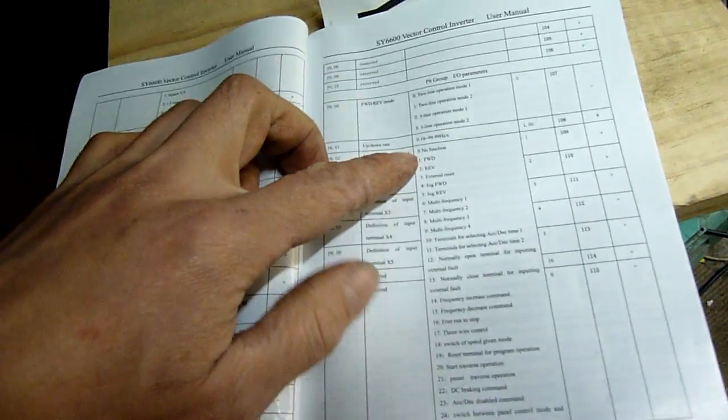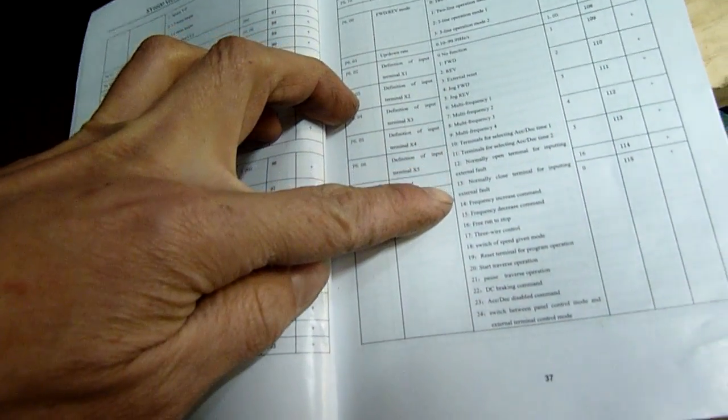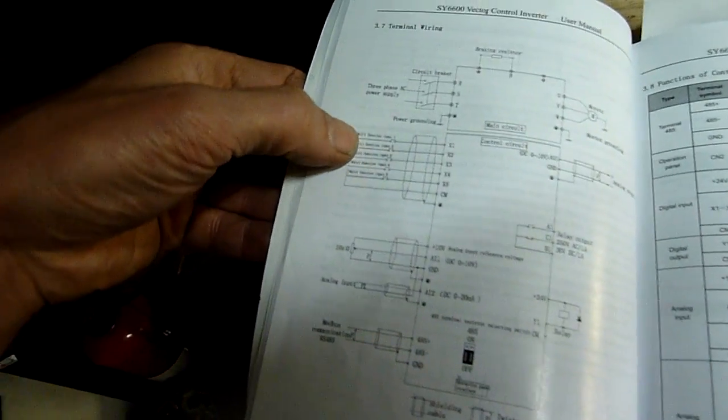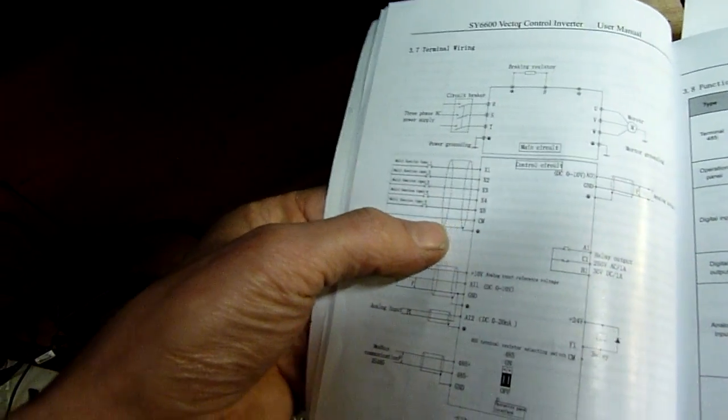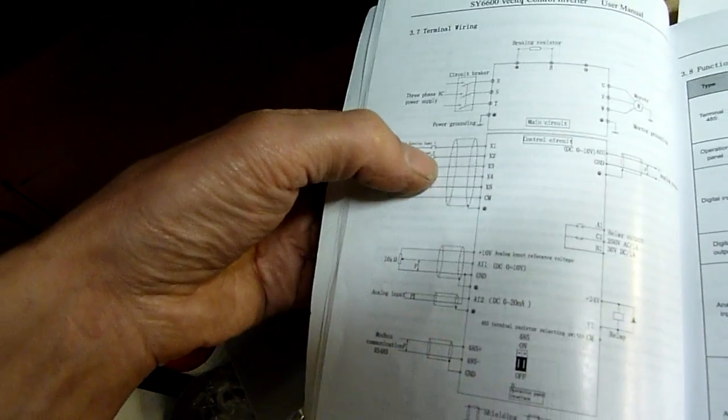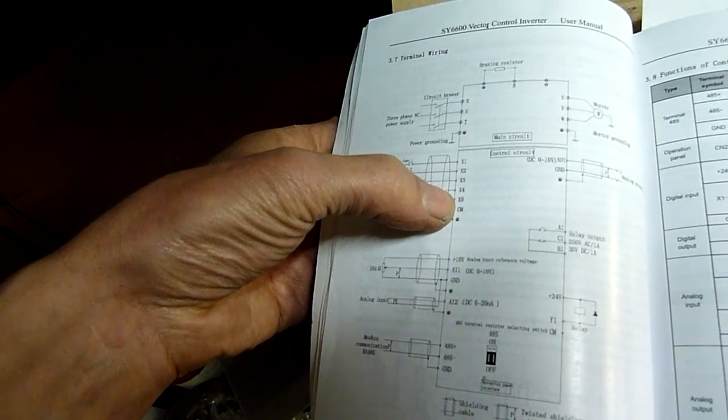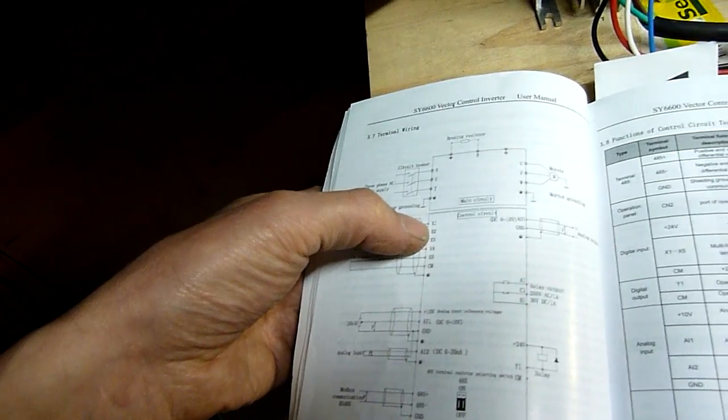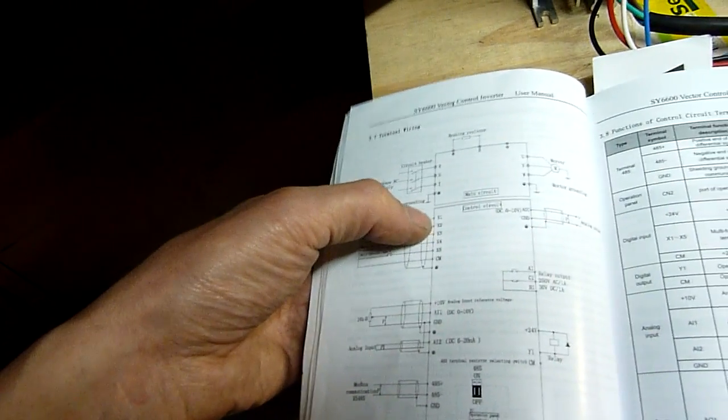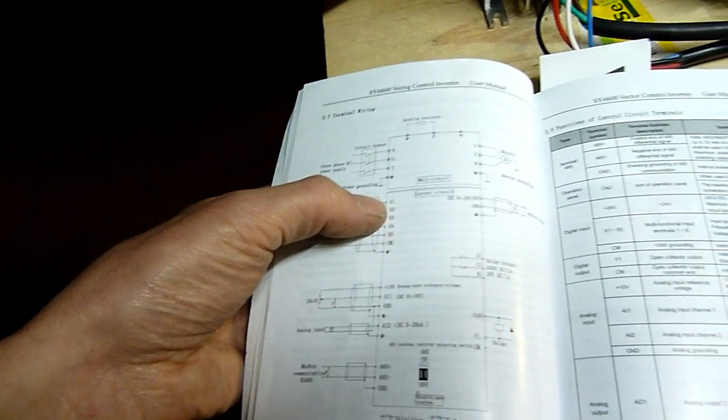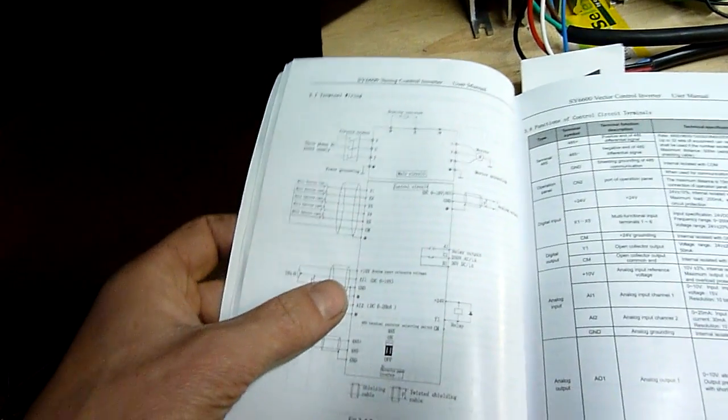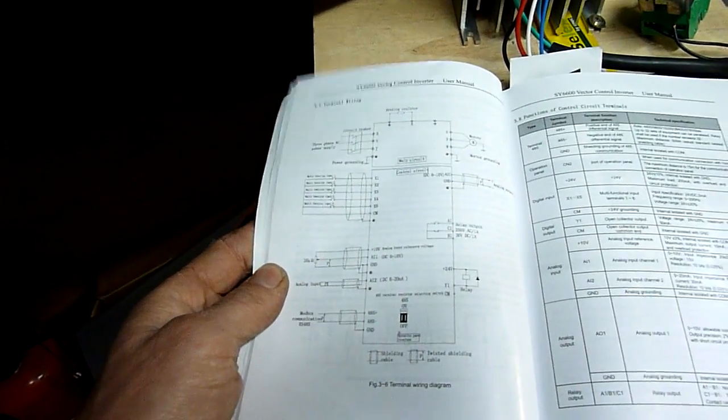See there you've got various assignments, you just assign the number that you want, and it'll do it. It does it just fine, I've played around with this a fair bit. Yeah, you've got common there, CM, going to one side of the switch, and then each one of those just assigns a, or you assign the command you want that terminal to do. I can change X1 from forward to reset, or anything really, I could tell it to just jog the motor. There's all kinds of things I could do.